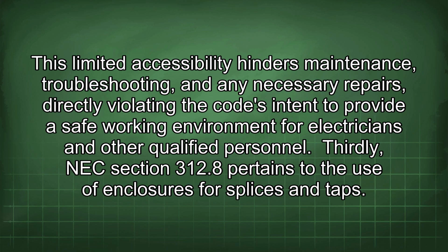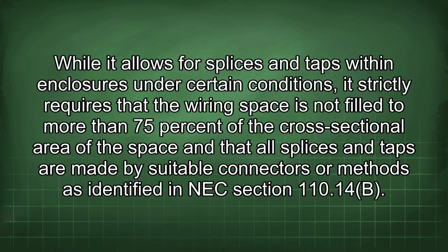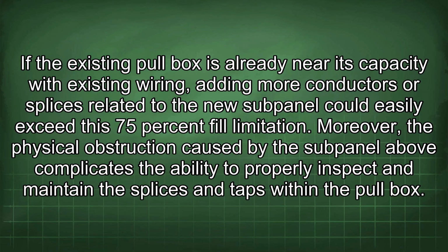Thirdly, NEC Section 312.8 pertains to the use of enclosures for splices and taps. While it allows for splices and taps within enclosures under certain conditions, it strictly requires that the wiring space is not filled to more than 75% of the cross-sectional area of the space, and that all splices and taps are made by suitable connectors or methods as identified in NEC Section 110.14(B). If the existing pull box is already near its capacity with existing wiring, adding more conductors or splices related to the new subpanel could easily exceed the 75% fill limitation. Moreover, the physical obstruction caused by the subpanel above complicates the ability to properly inspect and maintain the splices and taps within the pull box.